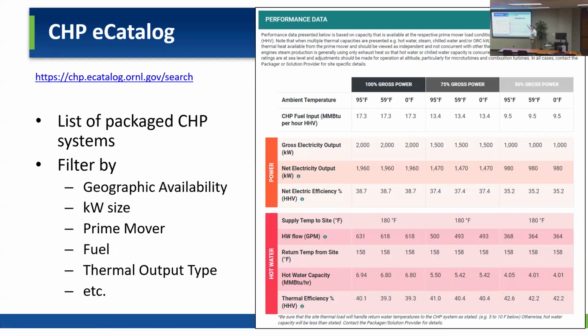All of the data is organized nicely. You can see, at 100% gross power—meaning full load—at outside temperatures of either 0 degrees Fahrenheit (really cold), 59 (cool), or 95 (Texas), what is our fuel input, in other words how many MMBTUs of natural gas this will consume, what electricity output it'll produce, what its hot water flow is, and the temperature differences between supply and return—or in other words, the hot water heating capacity.